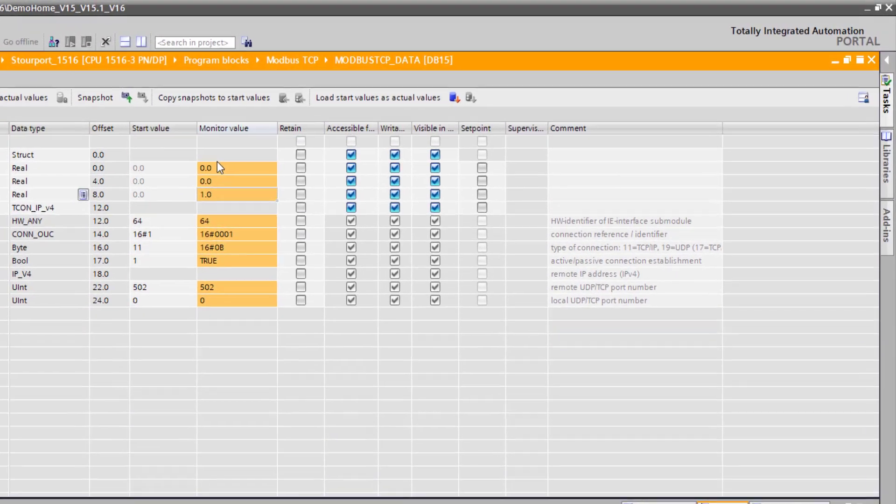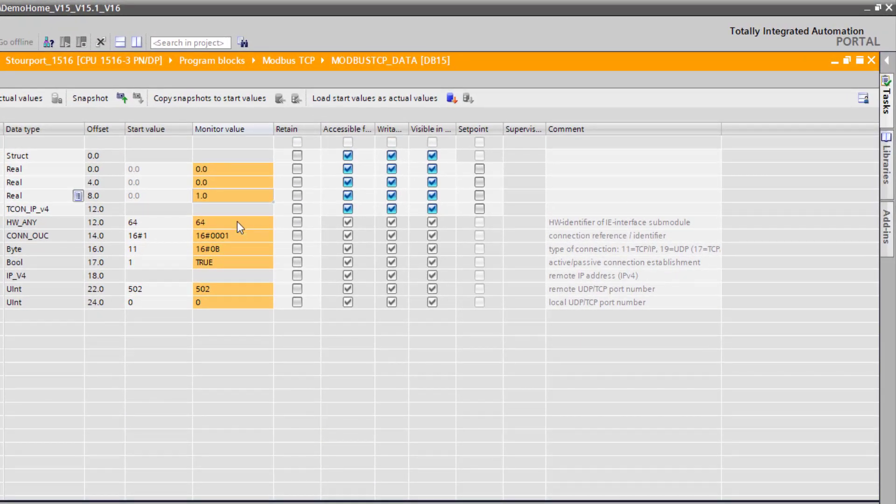So I'm going to show you the end goal. We're already communicating with Modbus TCP through this converter, which I'm going to show you in a minute. The data is not interesting because you can see here the density is 1 and there's no flow, but I have a connection.